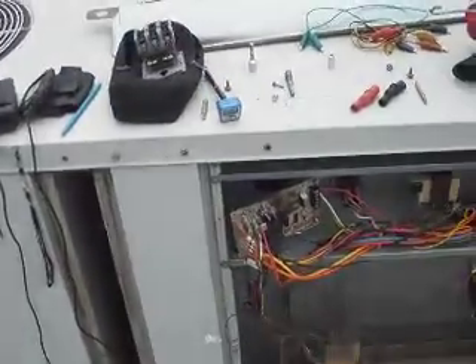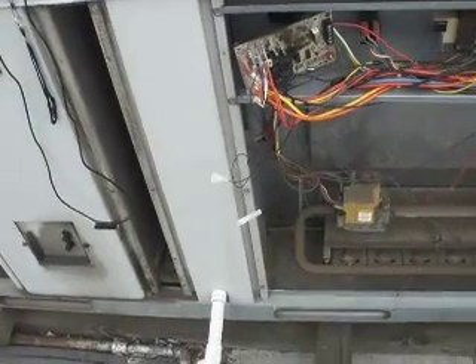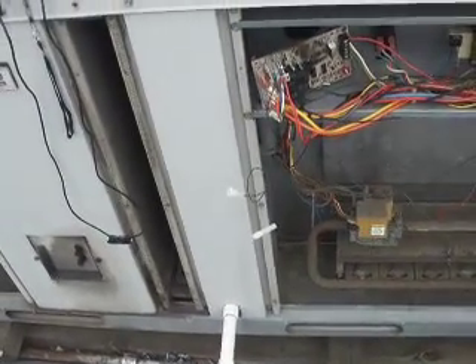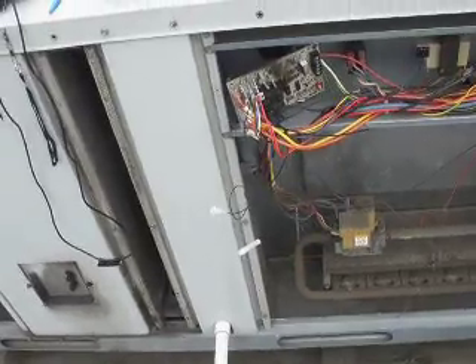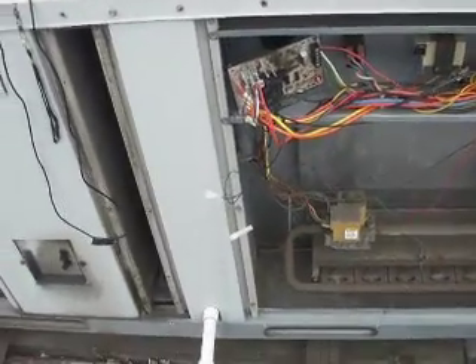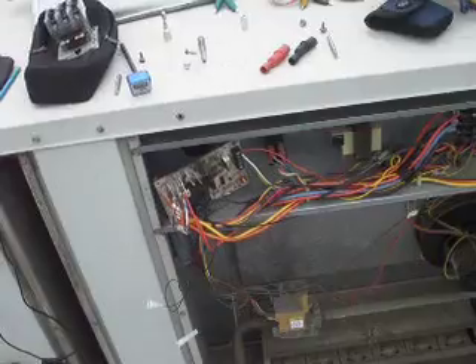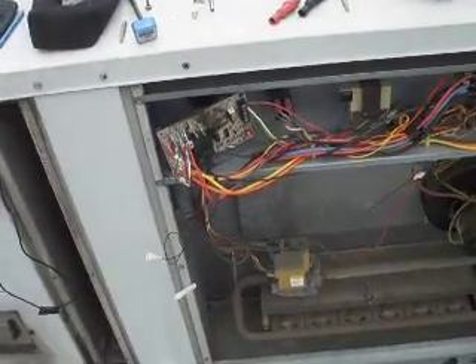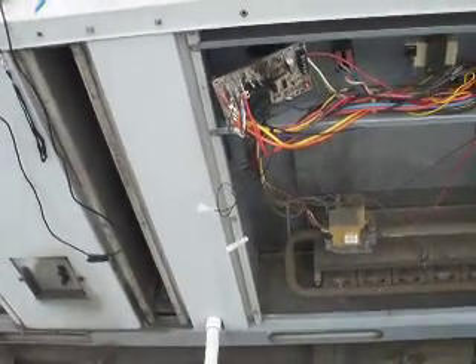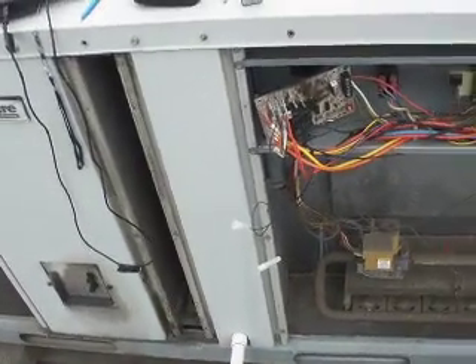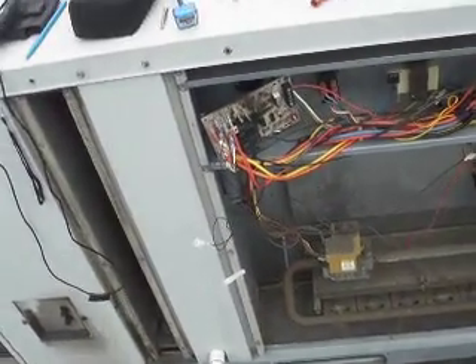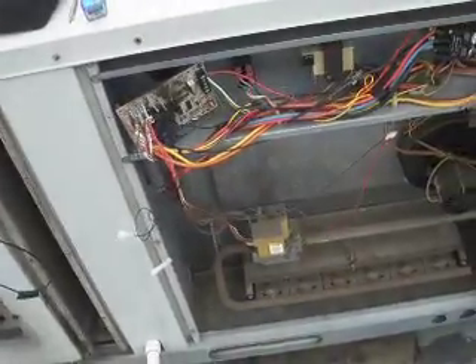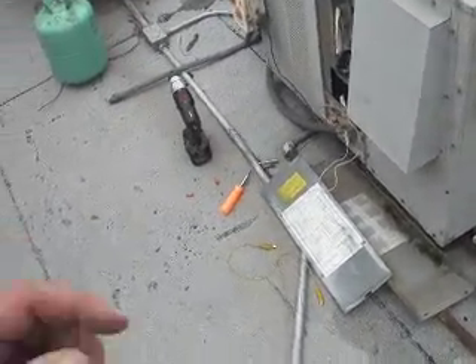The only real way to prevent something like this is by running an electrical surge box that will cut the equipment out. If you get any kind of a voltage surge or a power outage, it'll shut the equipment down. You can set it up on the unit individually, or on the main breaker panel, where it'll shut the equipment down and time out until the voltage is stabilized for a certain amount of time. Then it'll reset the equipment to start to run.